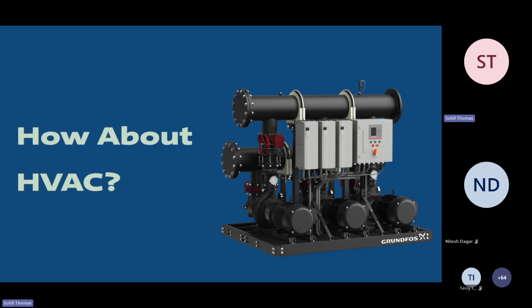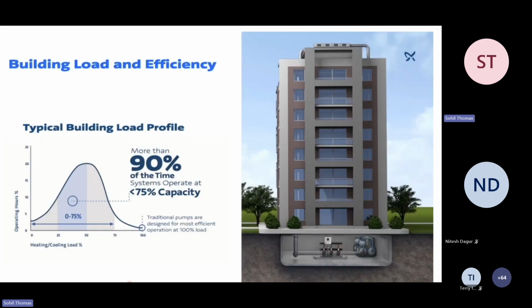We were talking about plumbing, but this goes to the HVAC situations too, because we see the same thing around the HVAC systems. This is a typical chiller application where more than 90% of the time, the system is operating at less than 75% capacity. But what do we do usually? We size the pumps to run at best efficiency point at 100% load. But what's actually happening is it's running at part load conditions, and you're not getting the best efficiency, and more energy is consumed for those kinds of applications.